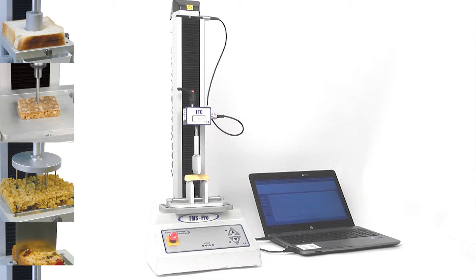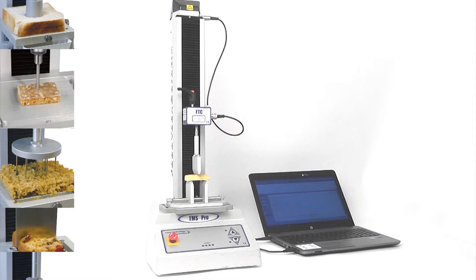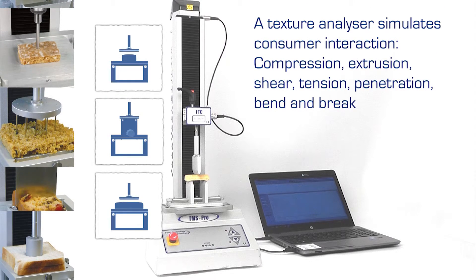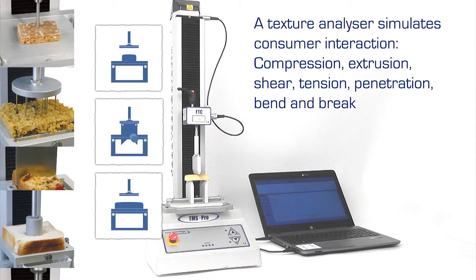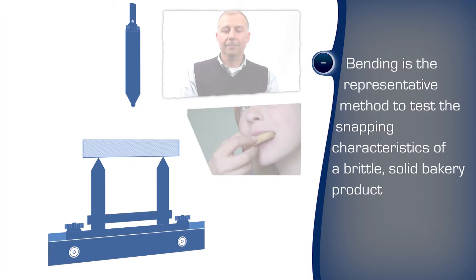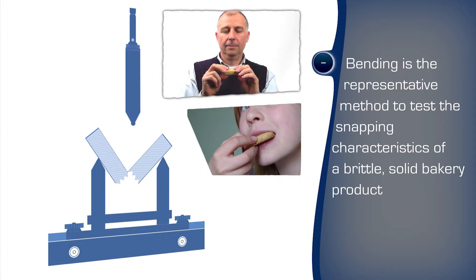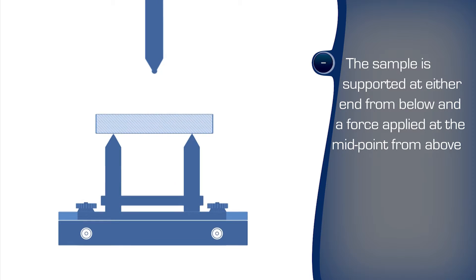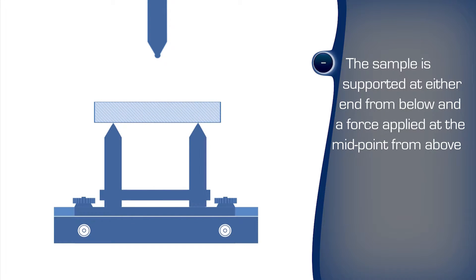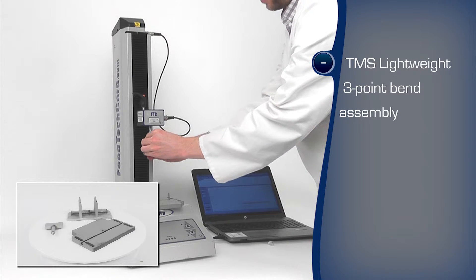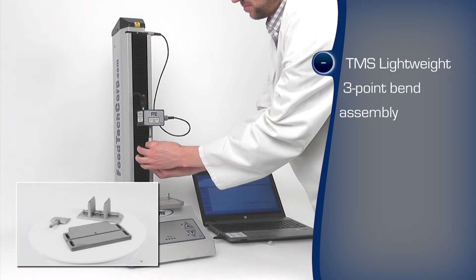A texture analyzer enables the measurement of attributes which reflect the consumer's experience by simulating the interaction: compression, extrusion, shear, tension, penetration, bend and break. Bending to break is the representative method for simulating a consumer flexing the product between the fingers and snapping it into smaller pieces. The hardness and firmness or softness attributes in flexible products may also be tested by compression, penetration, shear or tension. However, fracturability is best tested by snap, bend and break methods.